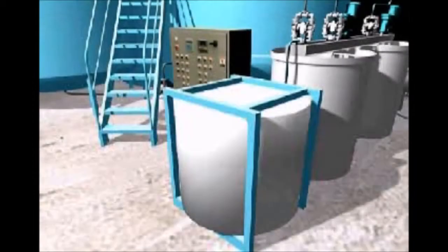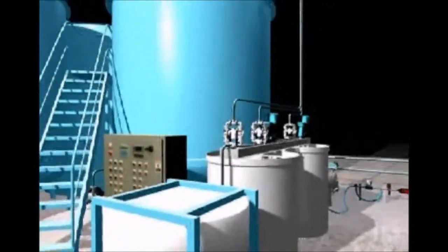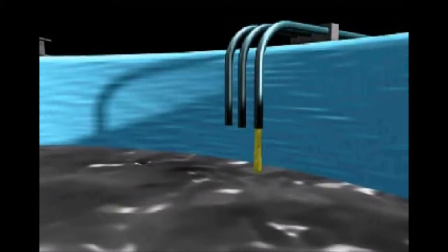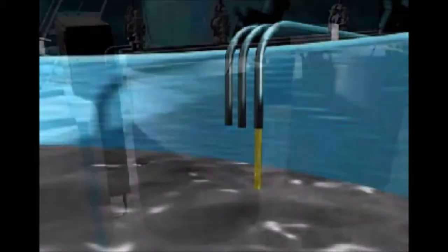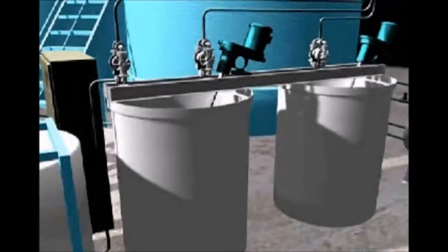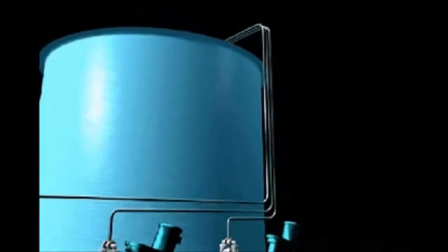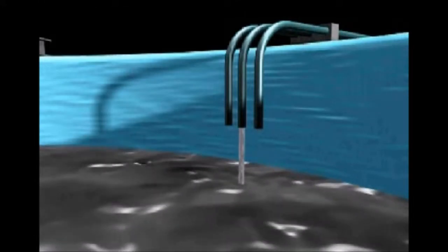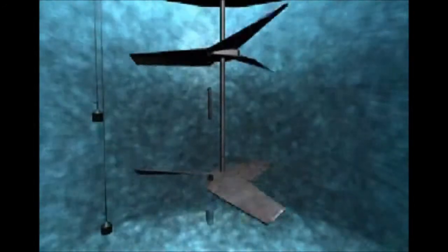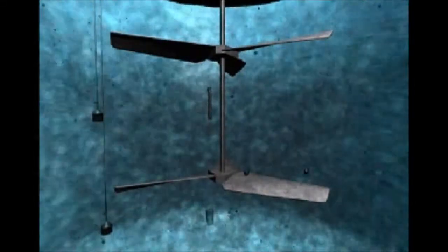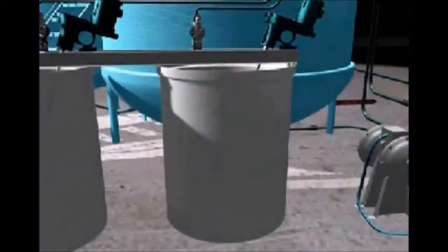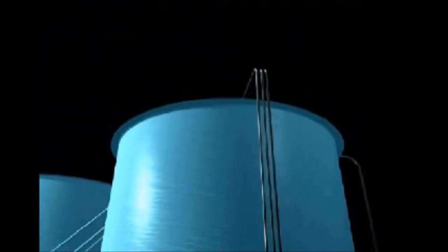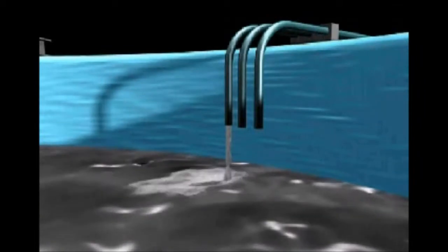The chemical addition phase starts with the addition of coagulant to the treatment tank. Depending on the nature of the wastewater, the coagulant can be added by pH or volume. After the coagulant addition is complete, the alkali pump is activated, which is deactivated once the proper pH has been reached, determined by the pH electrode and the analyzer's programmed set point. The addition of these chemicals permits the breaking of emulsions and coagulation of colloids, which appears as small particles separating from the wastewater. At this point, the recirculation stops, as well as the mixer in the treatment tank.